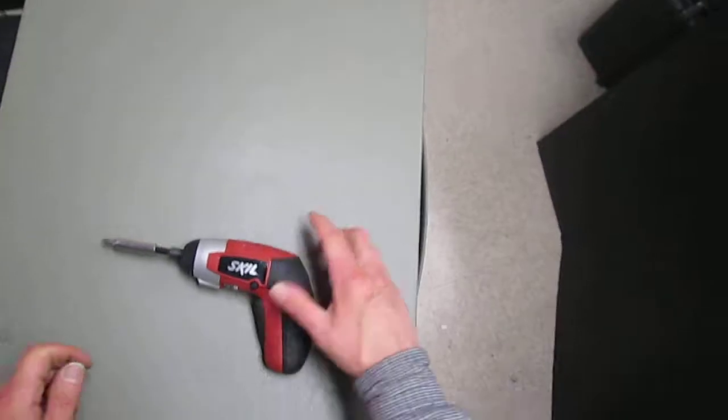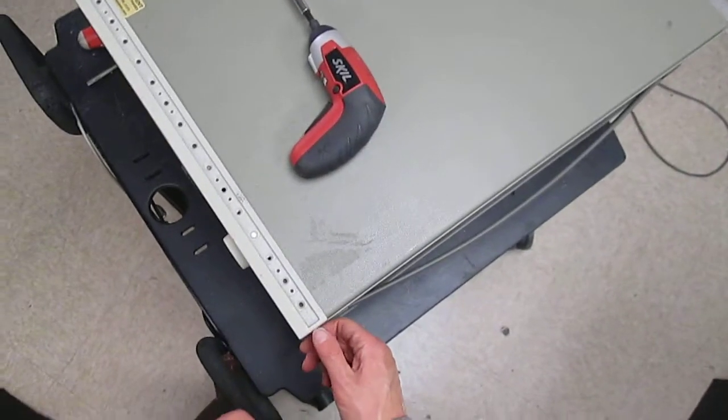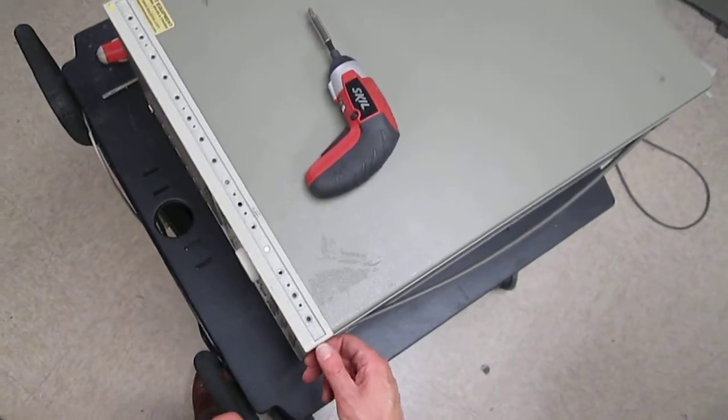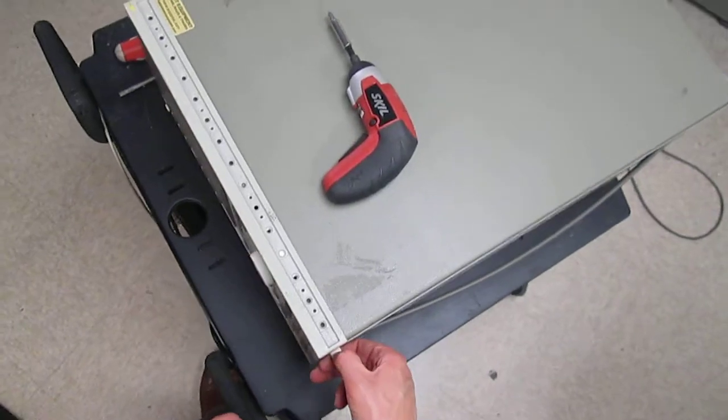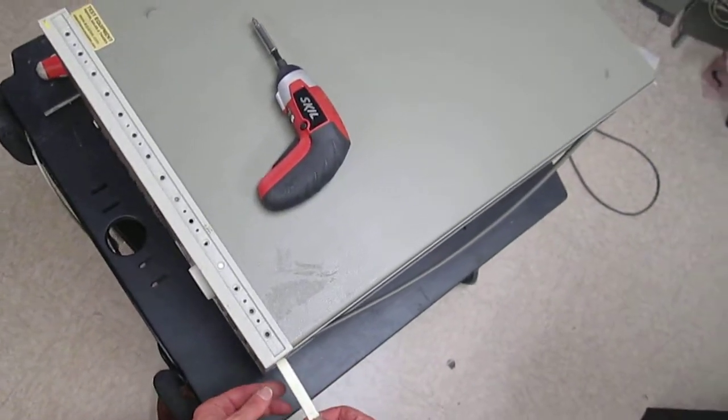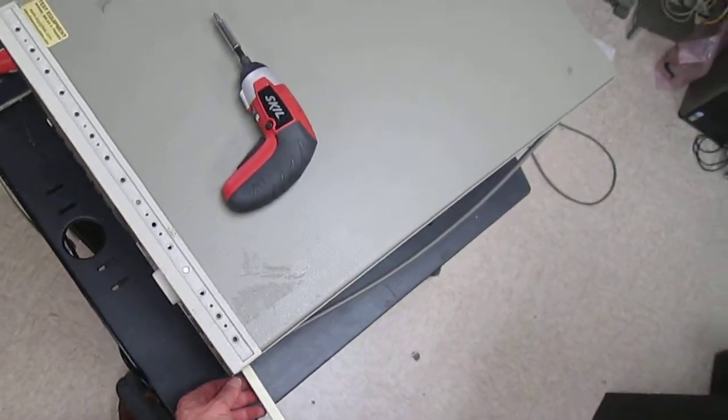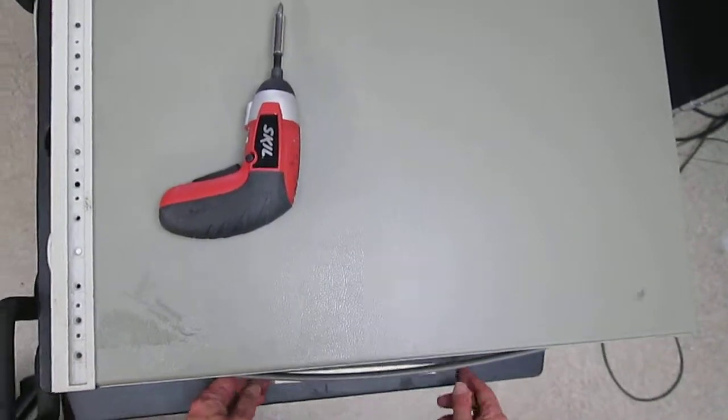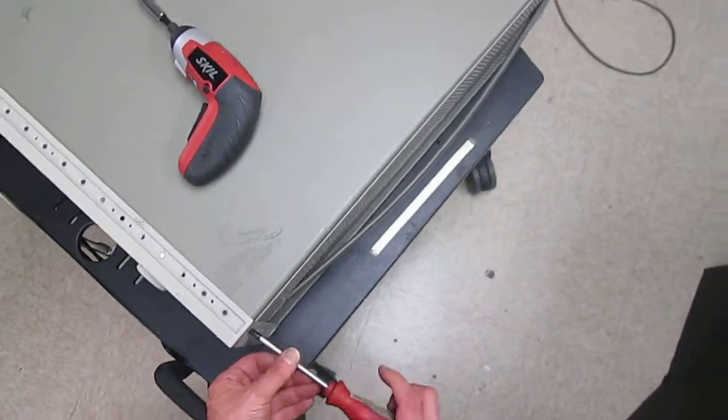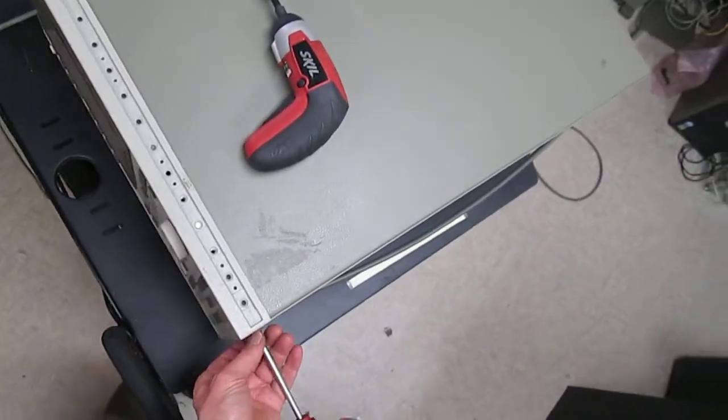Now, there are two more screws on each side of the analyzer that are hidden by the plastic trim. So, let's peel the trim off. It's just a sticky tape. Make sure to keep it clean so you can put it back on in place. There are two screws, and we remove both.